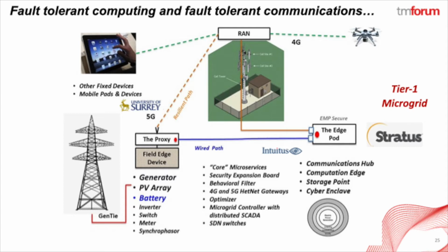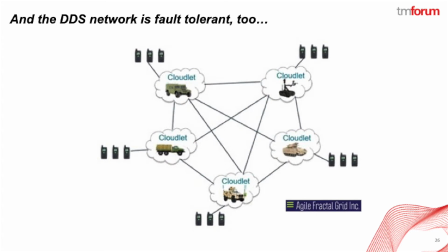Both wired communications and wireless 5G communications need to be employed for redundancy so that the entire grid is more fault-tolerant. We will use the industrial internet DDS protocols that were born in the weapons industry and are now standard for the electric power industry in the US. Using the DDS fault-tolerant event signaling, the same messages flow over multiple paths, but at the receiving end, only one packet is actually used. Thus, there is never an interruption in the flow of processing, even if one of the nodes is physically destroyed.